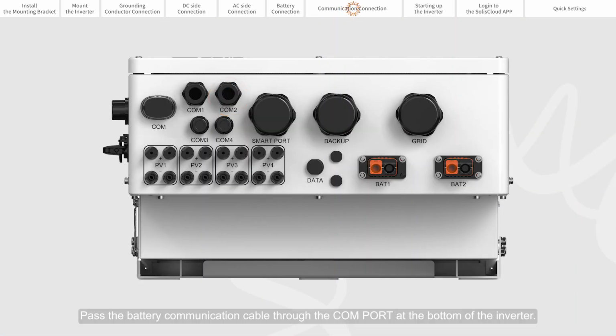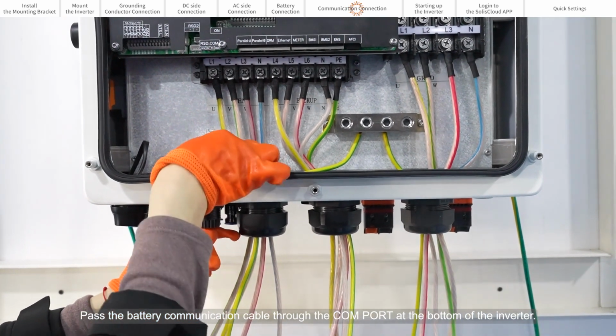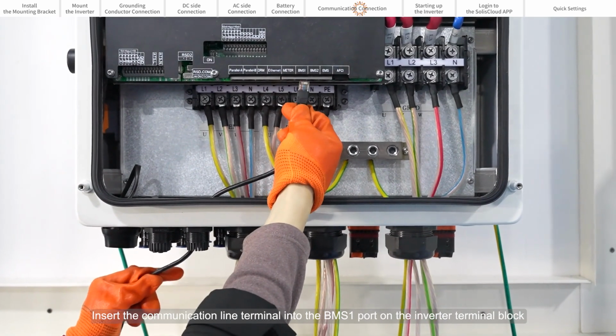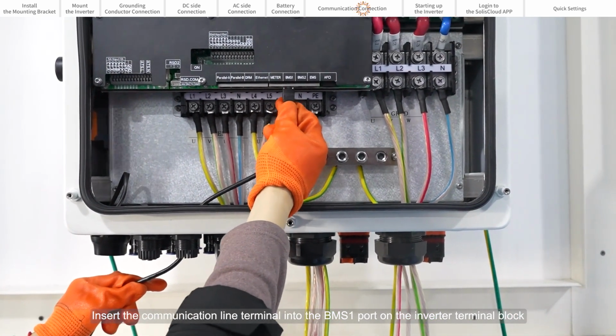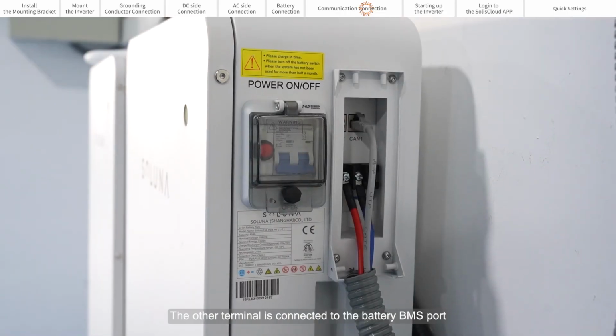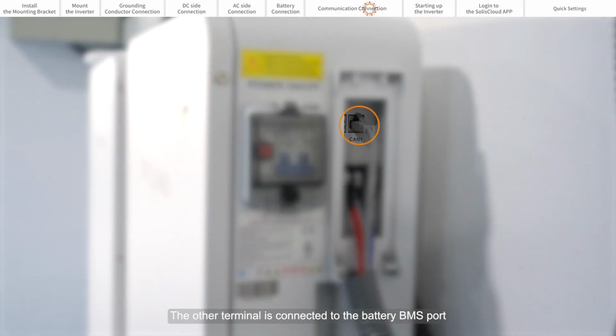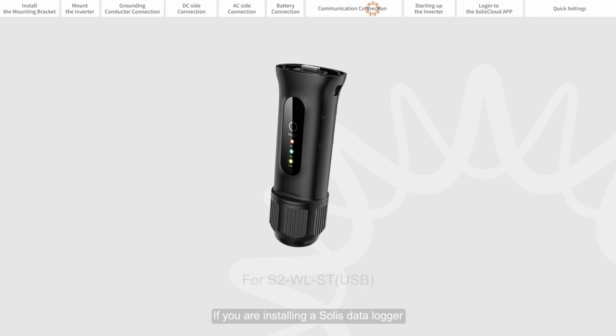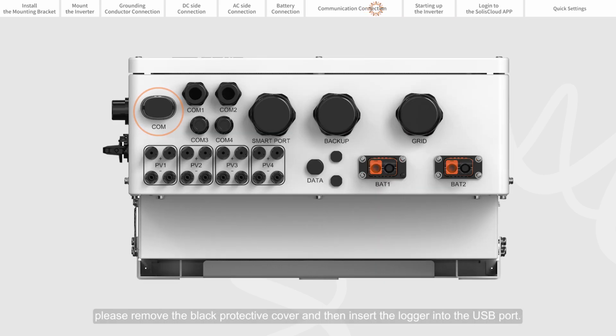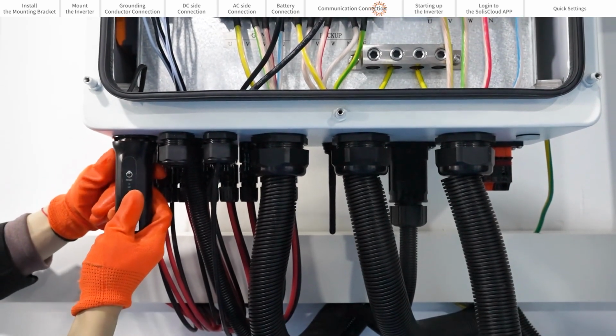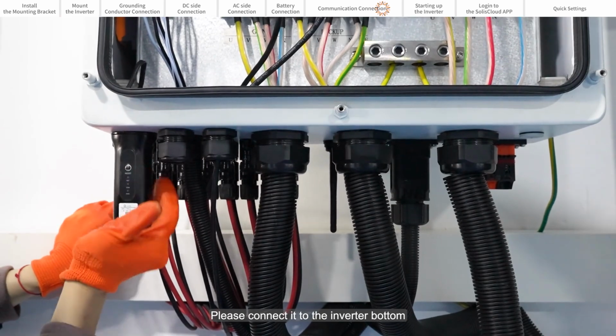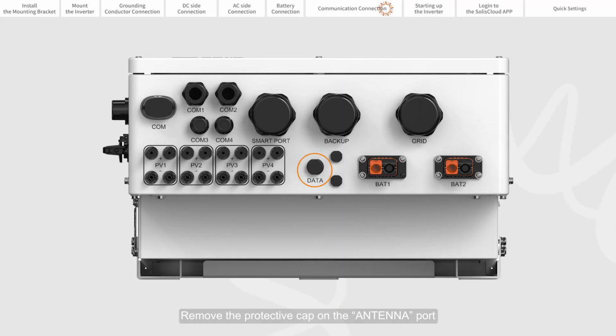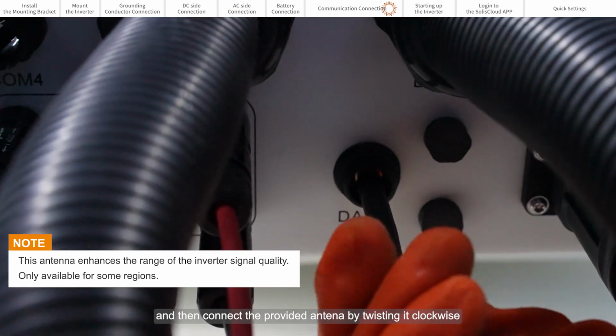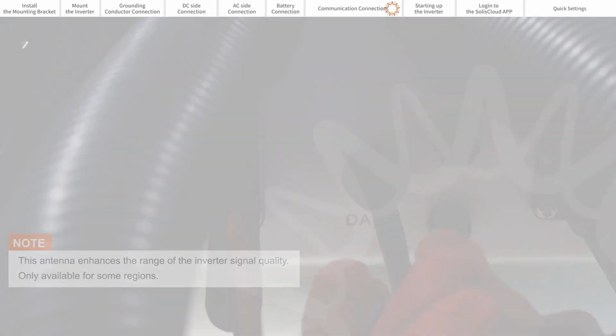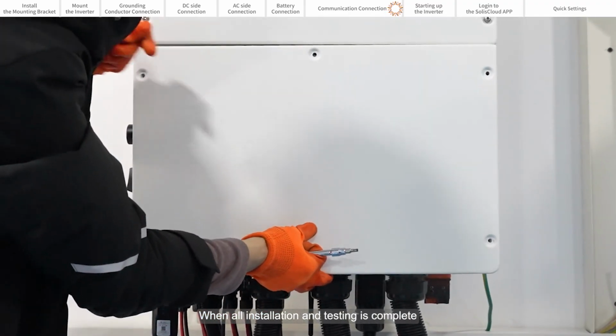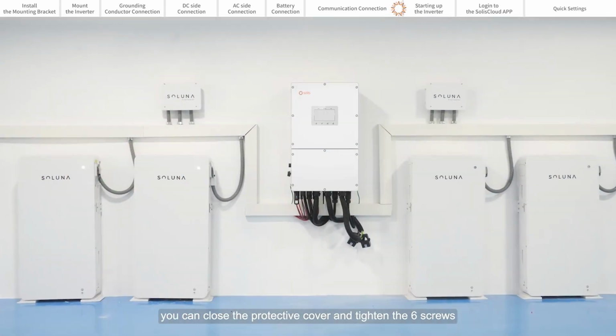Pass the battery communication cable through the COM port at the bottom of the inverter. Insert the communication line terminal into the BMS1 port on the inverter terminal block. The other terminal is connected to the battery BMS port. If you are installing a Solis data logger, please remove the black protective cover and then insert the logger into the USB port. Please connect it to the inverter bottom. Remove the protective cap on the antenna port and then connect the provided antenna by twisting it clockwise. When all installation and testing is complete, you can close the protective cover and tighten the 6 screws.